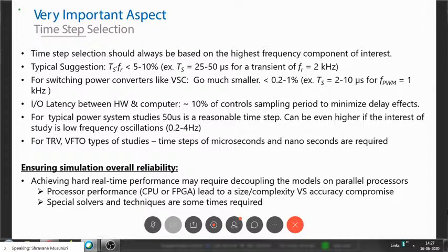I think I have a slide on that, which shows how the smaller the time step you go, the more nicely it captures the transient that appears across the bushing. This is very important for GIS kind of substations when they are doing the studies. My entire intention of mentioning this is, if you take a TRV study and try to put 50 microseconds or maybe 10 microseconds and do a study, yes, you will be able to see some transients, but we will not be sure if they are the transients that are going to be observed in the actual phenomena.